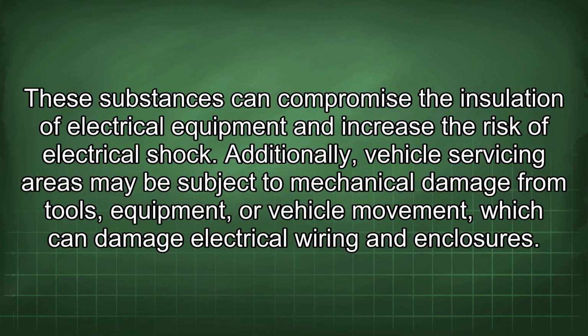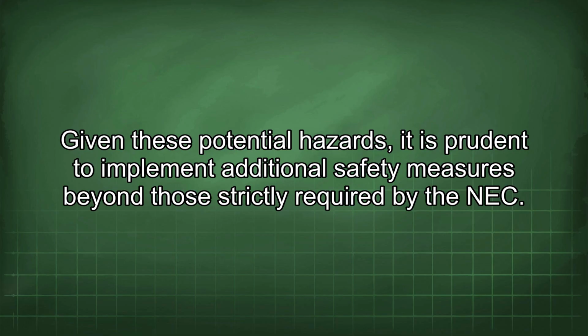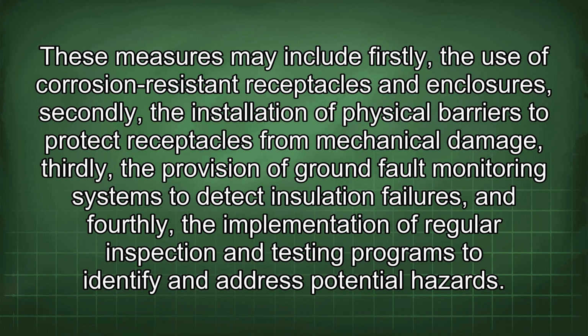Additionally, vehicle servicing areas may be subject to mechanical damage from tools, equipment, or vehicle movement, which can damage electrical wiring and enclosures. Given these potential hazards, it is prudent to implement additional safety measures beyond those strictly required by the NEC. These measures may include, firstly, the use of corrosion-resistant receptacles and enclosures, secondly, the installation of physical barriers to protect receptacles from mechanical damage, thirdly, the provision of ground fault monitoring systems to detect insulation failures, and fourthly, the implementation of regular inspection and testing programs to identify and address potential hazards.